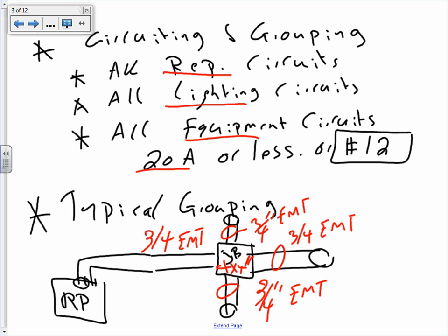Any questions, guys, about typical grouping of circuits? Okay, now I want you to keep this in mind, and these are the things that I suggest you group. Now, you have an air handling unit. Is it a good idea to group the feeder for an air handling unit with other circuits? No, bad idea. We're talking about 20 amp lighting circuits, 20 amp receptacle circuits, and 20 amp equipment circuits. That's it. That's where grouping makes sense. These are the types of circuits that we're talking about, guys. Can I have thumbs up, Chad? We fully understand. We're not grouping the air handling unit.